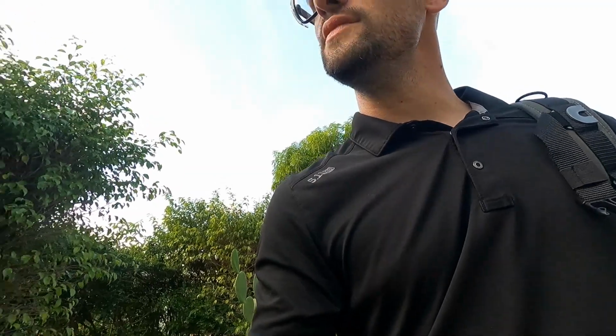As soon as I walked in, I heard that little short happen in the panel. It was easy enough for me to safely remove the panel, because it is live, obviously, and get all that hooked back up. About half their breakers were jarred loose, so got those back in position, and now everything outside of just the air conditioners is working properly. But operations were checked, and we are in fact cooling. I can't just pop those breakers in and walk away, I need to make sure that they are in fact operating and cooling before I step foot off this job. So we did that. Everything's good, and another job done.